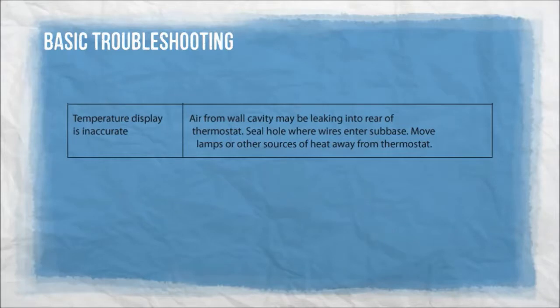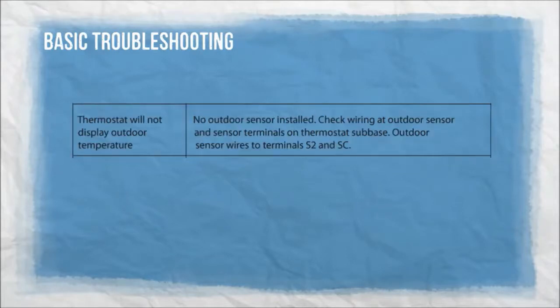Temperature display is inaccurate. Air from the wall cavity may be leaking into the rear of the thermostat — seal the hole where the wires enter the sub base. Move lamps or other sources of heat away from the thermostat. Thermostat will not display outdoor temperature: no outdoor temperature sensor installed. Check wiring at the outdoor sensor and sensor terminals on the thermostat sub base. Outdoor sensor wires to terminals S2 and SC.